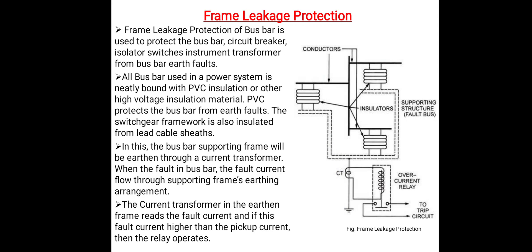In the figure of frame leakage protection, the metal supporting structure or fault bus is grounded through a current transformer, and the secondary of the current transformer is connected with the overcurrent relay. Under normal working condition, the relay remains inoperative. But a fault involving a connection between a conductor and the grounded supporting structure will result in current flow to ground through the fault bus, causing the relay to operate. The fault current flows through the current transformer to the grounded path, and when current flows through the secondary of the CT, it also flows through the overcurrent relay. When current flows through the relay, the contacts close and send information to the circuit breaker, which trips the circuits and isolates the healthy section from the faulty section.